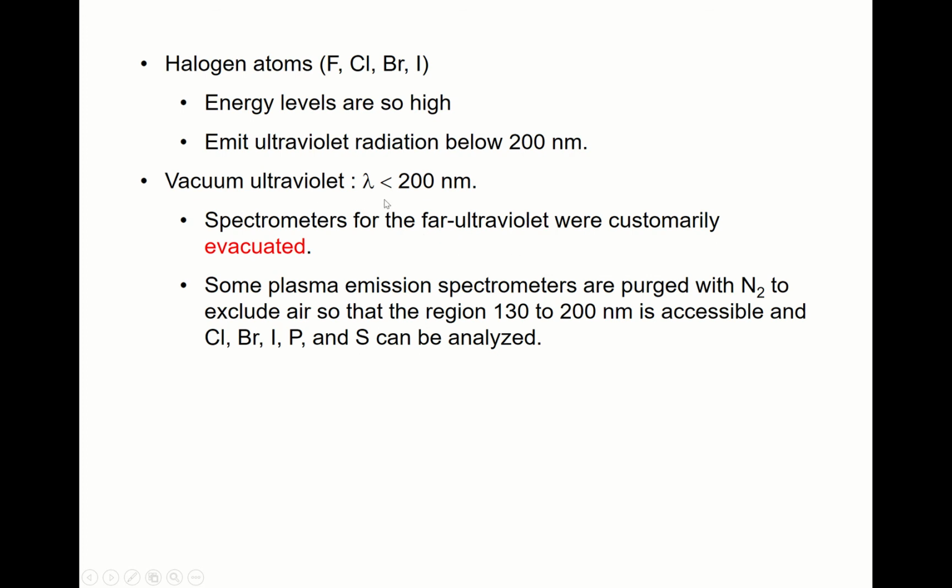In the presence of air, this radiation is scattered so much that the signal will be very weak. So spectrometers for the far ultraviolet were customarily evacuated.